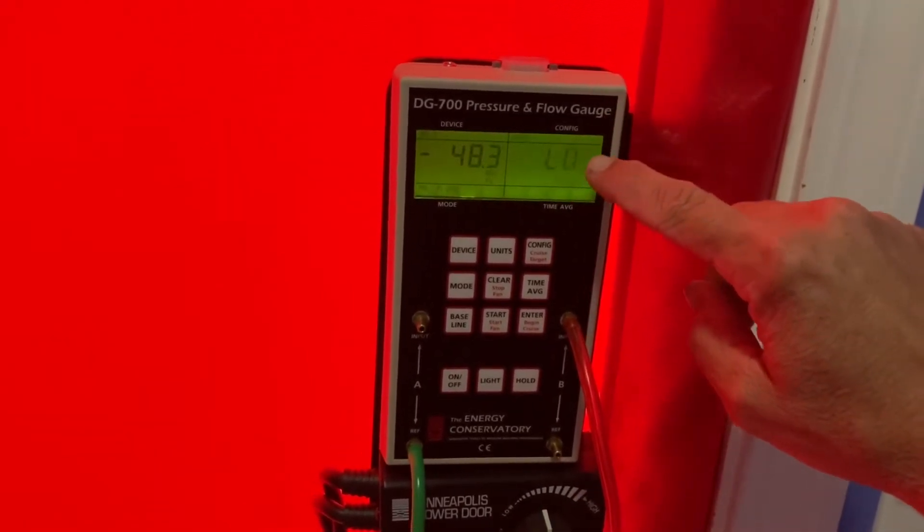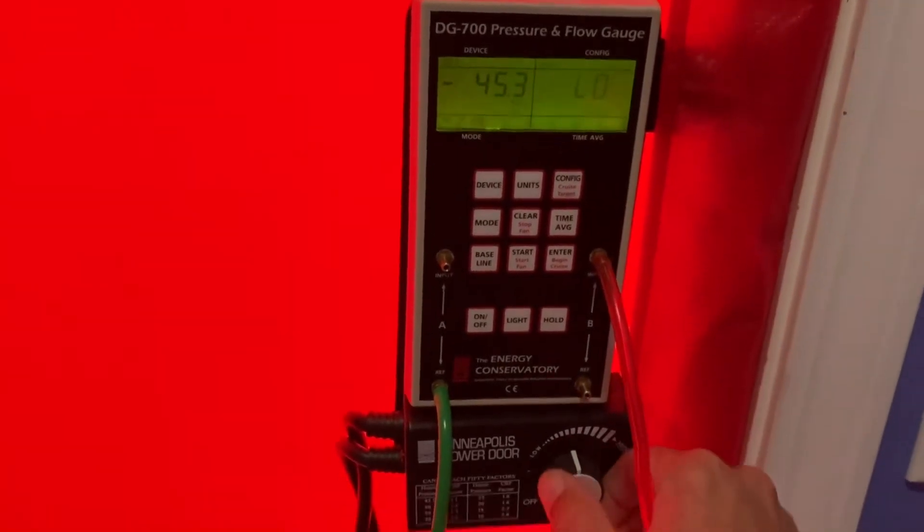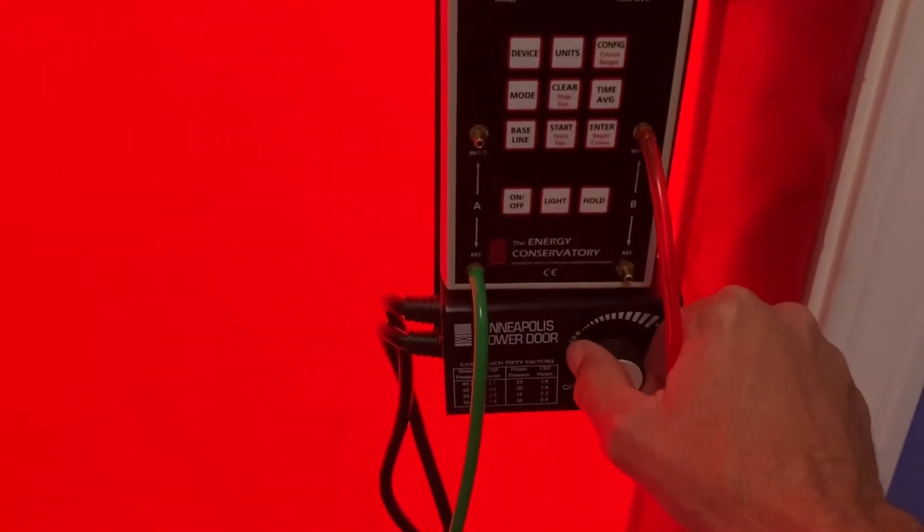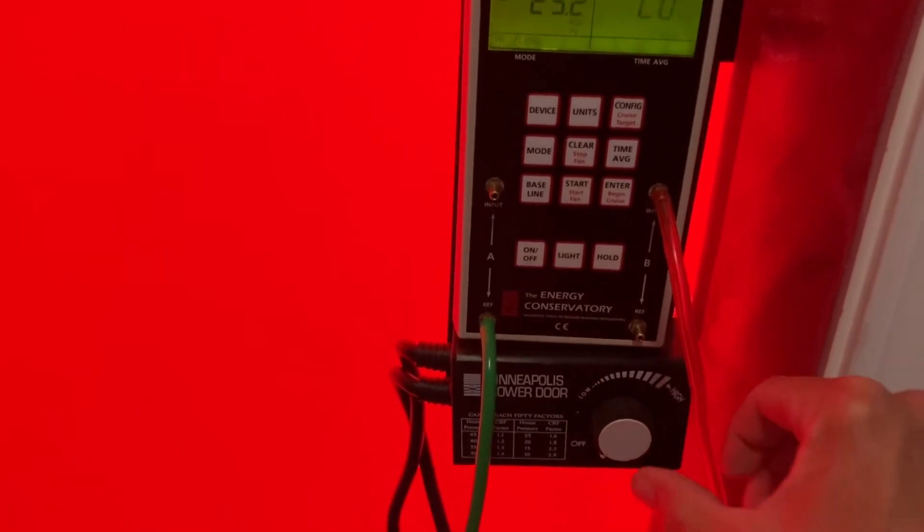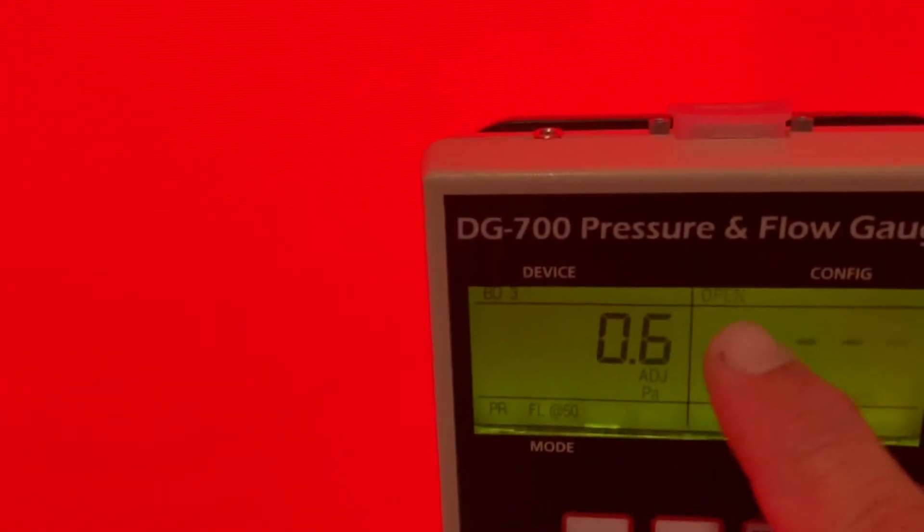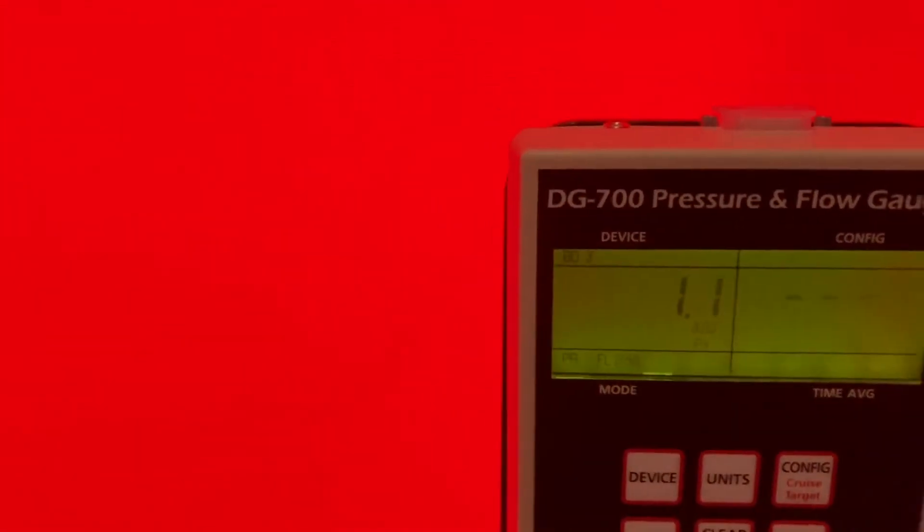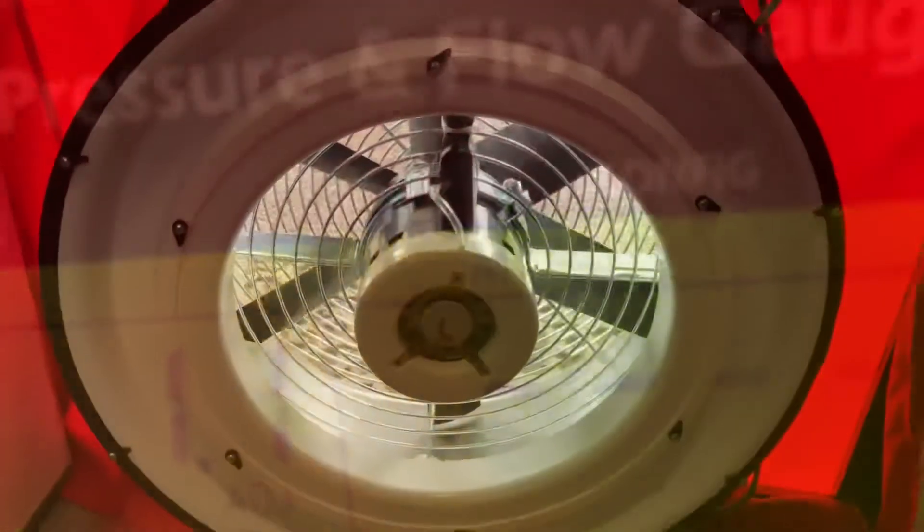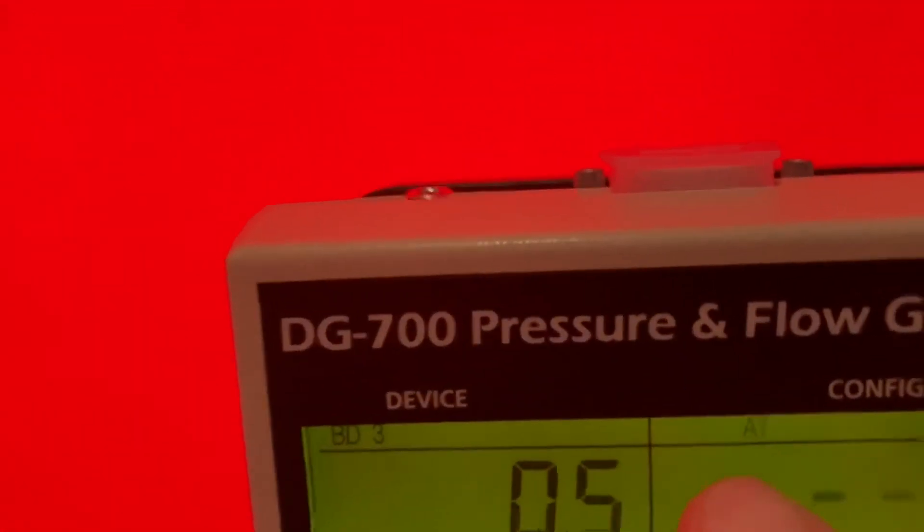So what we'll do is we'll add a ring to the fan and we'll reconfigure the manometer. We're going to add the A ring to it, so we need to reconfigure the manometer. We'll do that by pushing the configure button once until instead of saying open it says A1. Then we'll add the A1 ring to the fan as well so they are matching with each other.